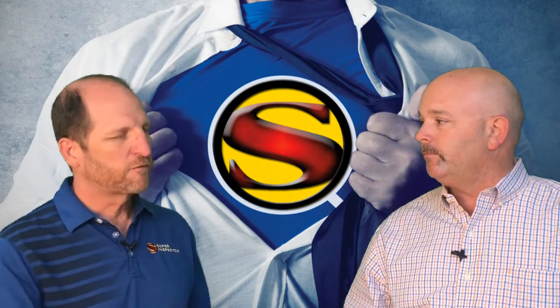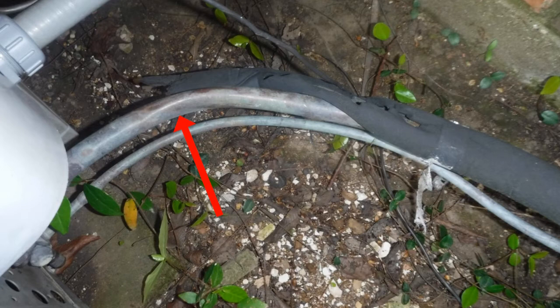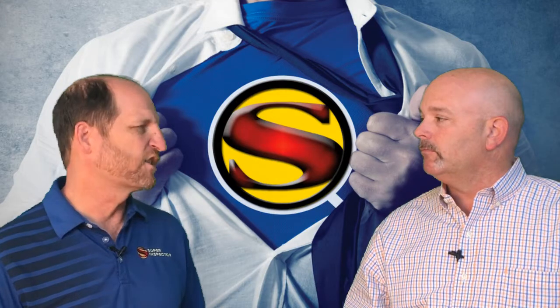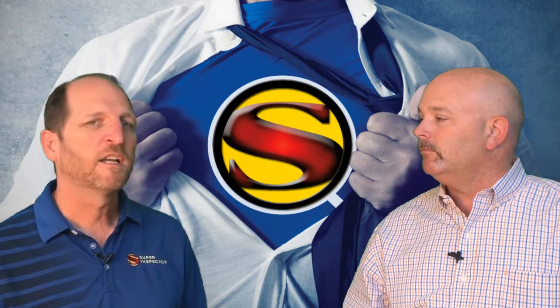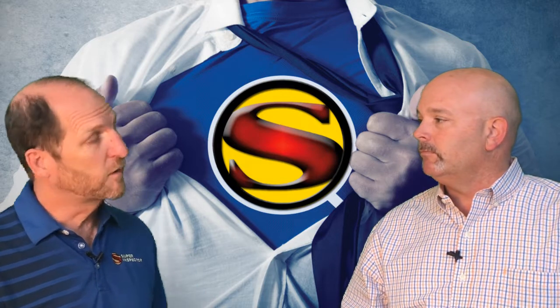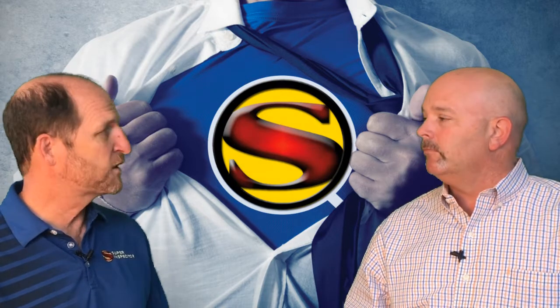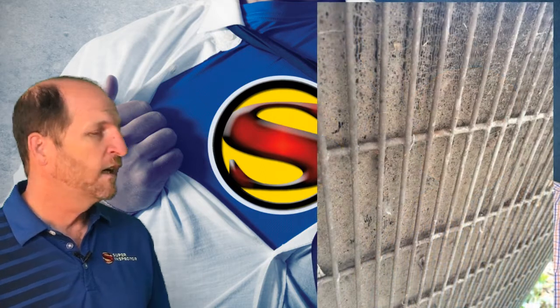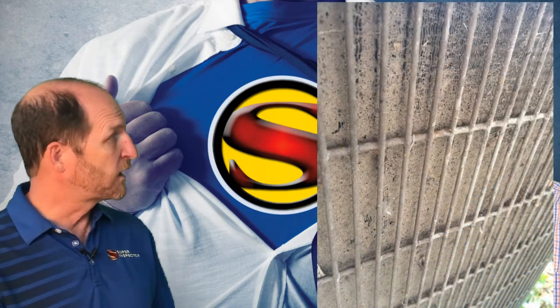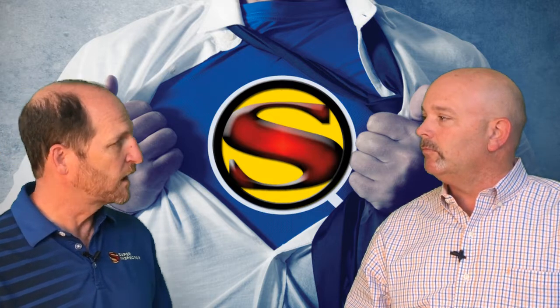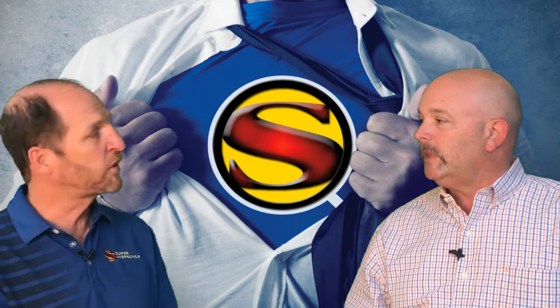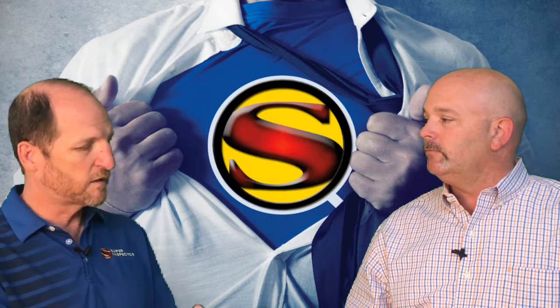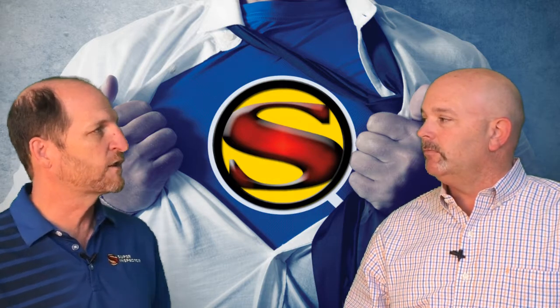like the refrigerant pipe that comes out of the wall and goes to the condensing unit. One of those two pipes should be insulated. Much of the time that insulation is either missing or deteriorated. We'll look at the coil. A lot of times it's dirty, it needs to be cleaned. And if the condensing unit is not level, we always recommend that it be leveled. It's going to perform better when it's level because there's oil in the compressor motor. So we want that to be level so it's not pooling to one side of the motor.